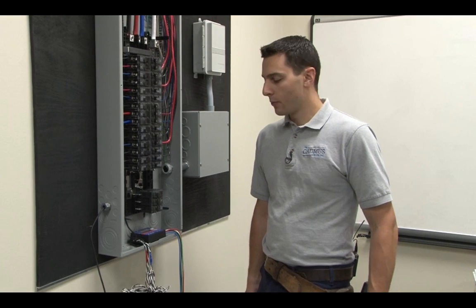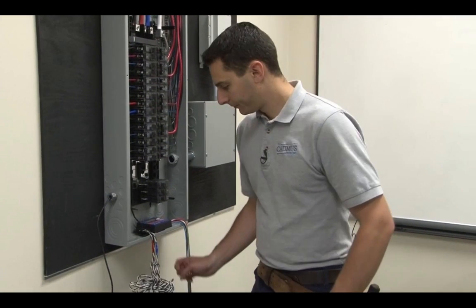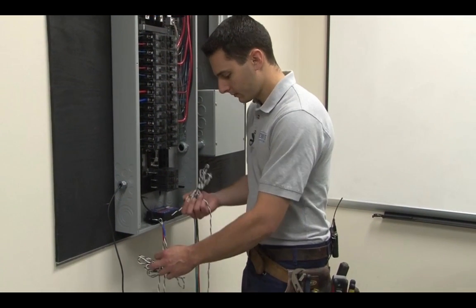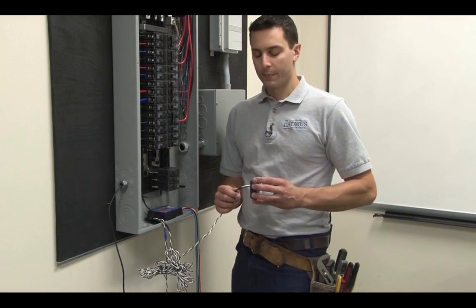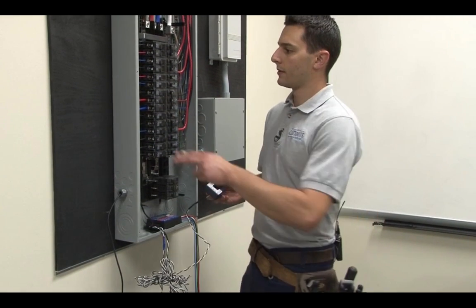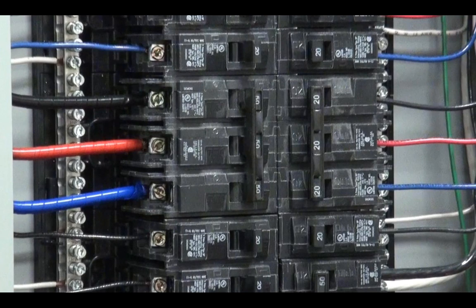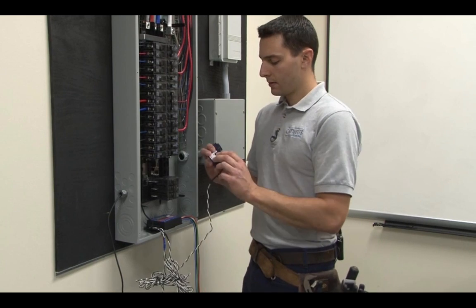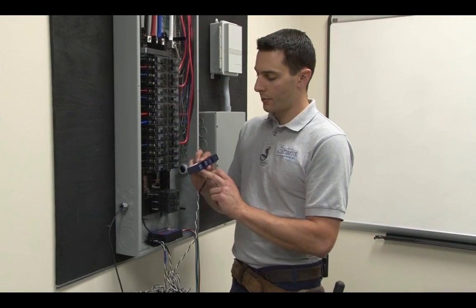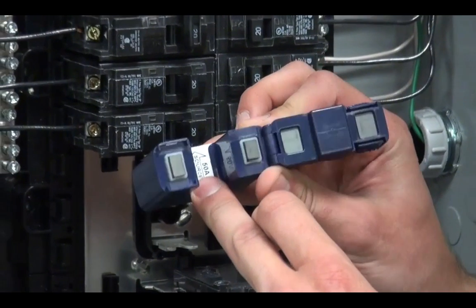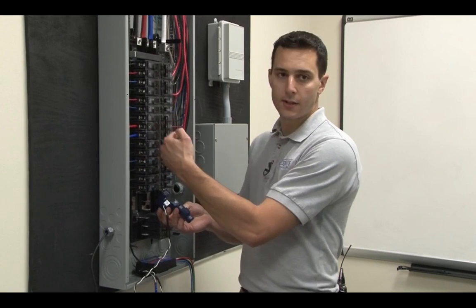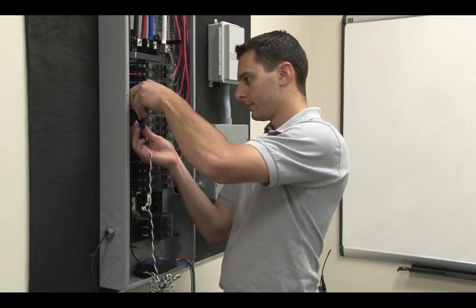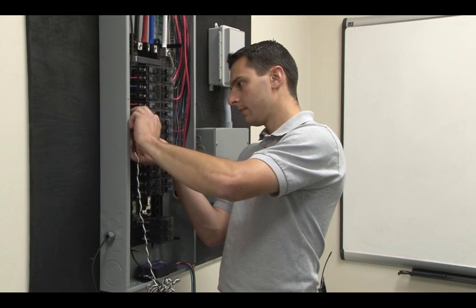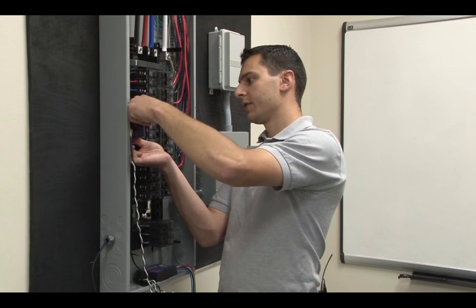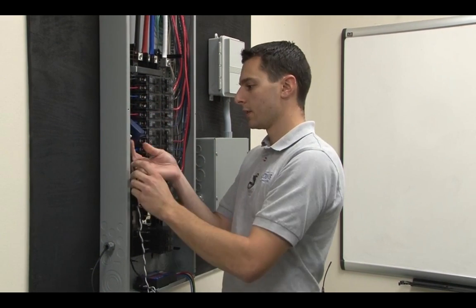Now that everything is wired to the Wattnode, we can begin connecting our CTs to the phase conductors. We will start with the black phase A CT. This will go around the black conductor on our circuit. Once again, this particular CT is directional, so we want to make sure the arrow faces the source, or in this case, faces the center of the panel board. And this CT just clips shut so we know we have a secure connection.